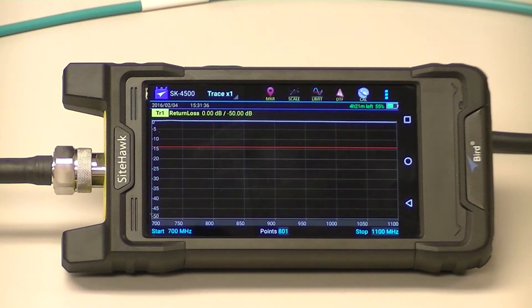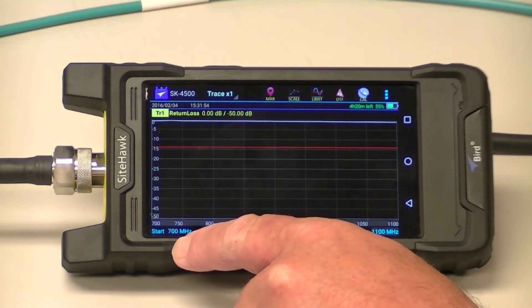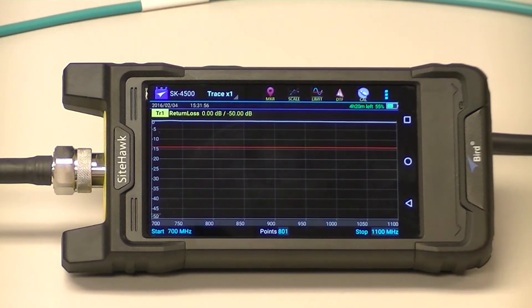I'm going to go through the procedure on calibrating the SiteHawk before you perform a measurement. Anytime you do a distance to fault, a return loss sweep, or measure and match mode, you want to set up all your parameters of the SiteHawk, such as your frequency. In this case, I'm set from 700 megahertz to 1100 megahertz.